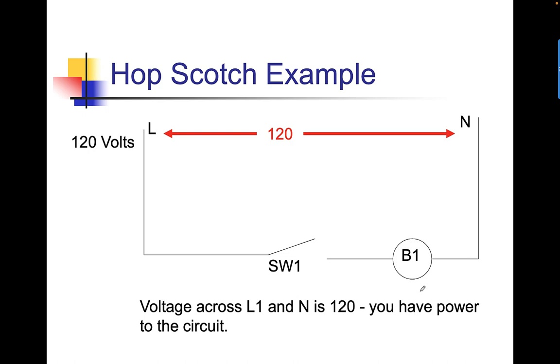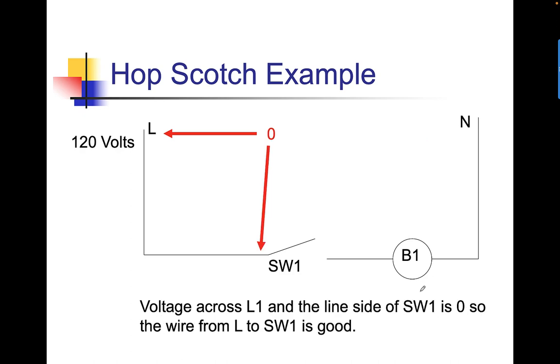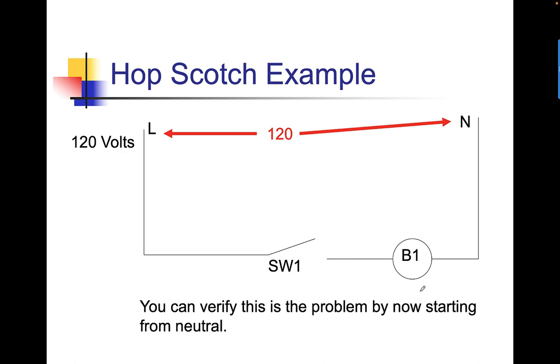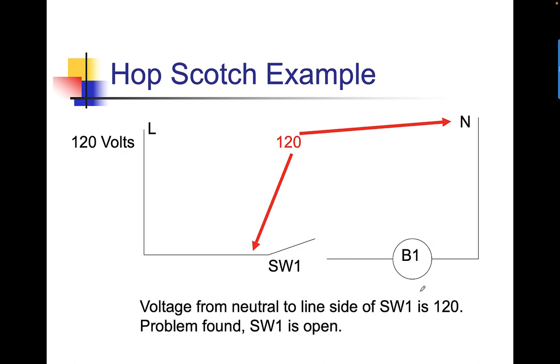In this example, we're testing voltage across L and N — it's 120 volts, so we have power to the circuit. Voltage between L1 and the line side of switch one is zero, so that wire is good. Voltage across L1 and the load side of SW1 is 120 — switch one is open. Remember, voltage across an open switch is always source. We can verify that by starting from neutral and working backwards to the switch — we come across switch one again and it's 120. You might think you can just look and see the switch is open — no, you can't. It's inside a container, a piece of metal or plastic, so you won't be able to see if that switch is actually open or closed. Problem found: switch one is open.